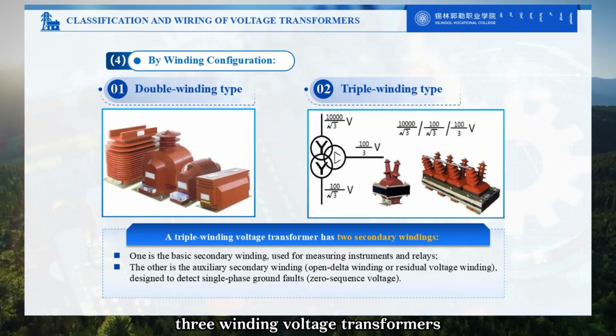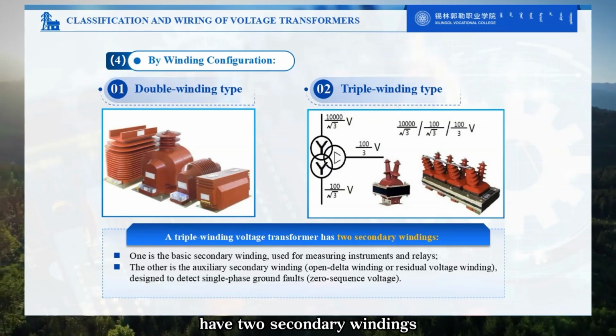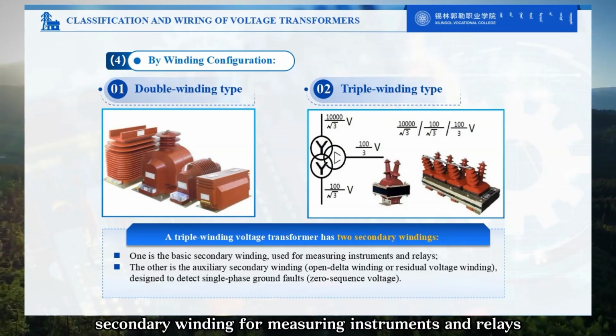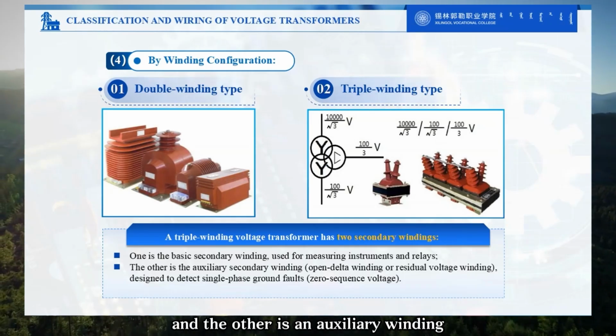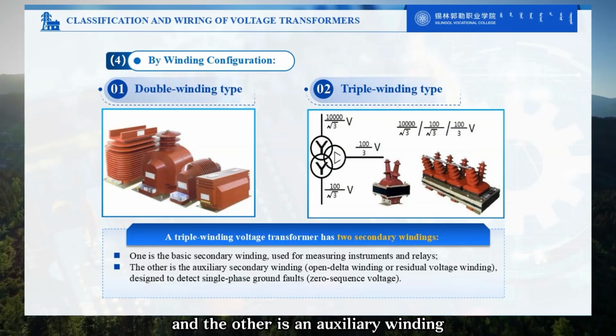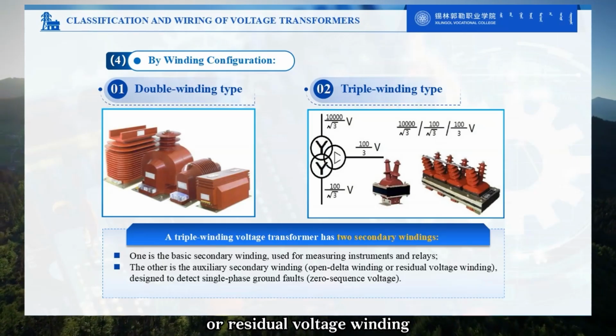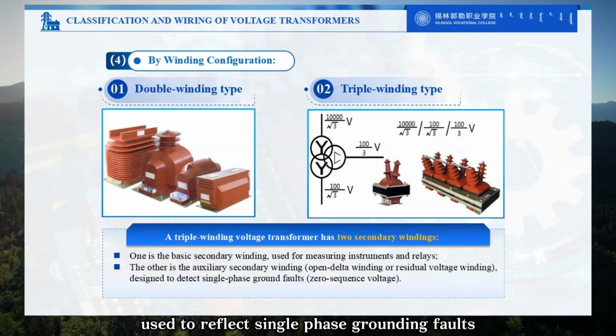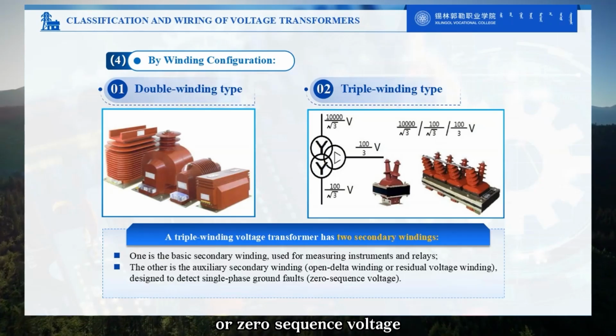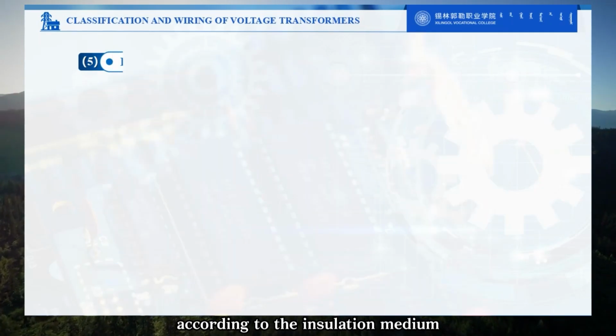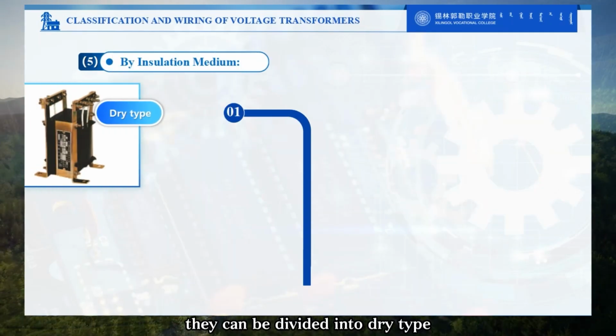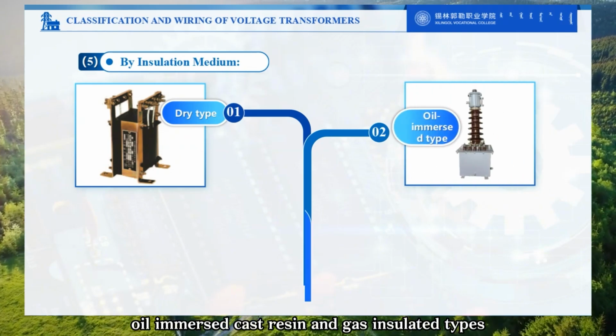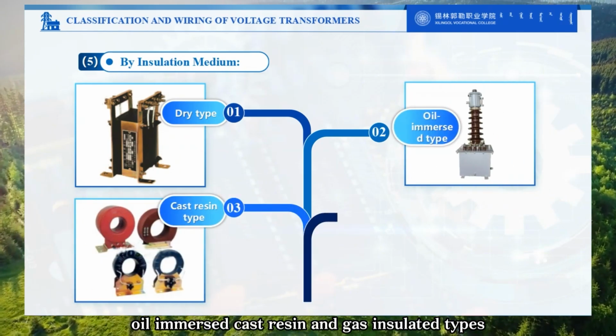Three-winding voltage transformers have two secondary windings. One is the basic secondary winding for measuring instruments and relays, and the other is an auxiliary winding, namely the open delta winding or residual voltage winding, used to reflect single-phase grounding faults or zero-sequence voltage. According to the insulation medium, they can be divided into dry-type, oil-immersed, cast resin, and gas-insulated types.